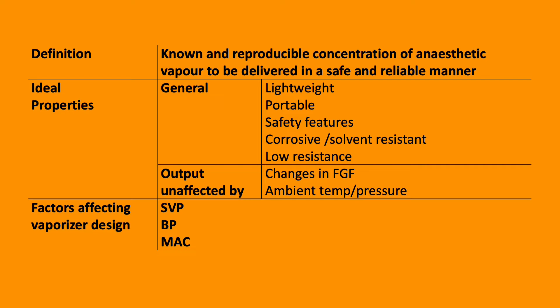Ideal properties should be: lightweight, portable, have clear safety features, be corrosive and solvent resistant, be low resistance, and the output should be unaffected by changes in fresh gas flow and ambient temperature and pressure.